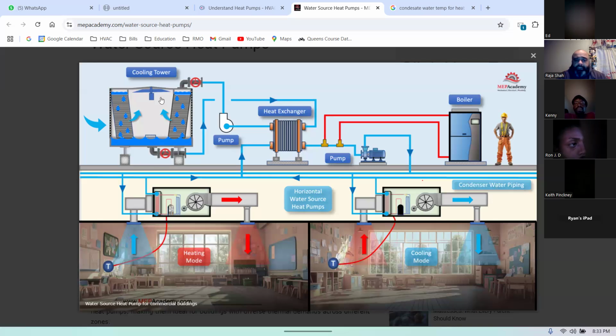So we just wrote that up recently when we were there. So in the wintertime, this tower is not going to be running fully. You're still going to have water going through it. Normally, Frankie, you're going to have a bypass here. Instead of going to the top, it's going to go through the bottom. Because it's so cold outside, it doesn't need to trickle down and lose that heat. And remember, we're using this water now for heat, for heating the boilers. So when it comes through here, it's going to be picking up...